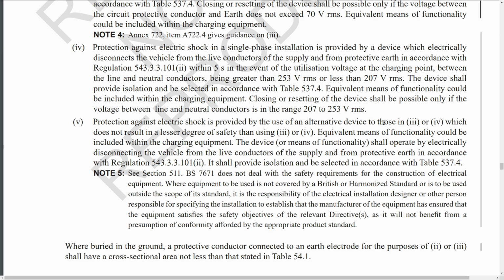Now, this can happen by having an unbalanced three-phase system, because when you have an unbalanced three-phase system, the neutral point is not actually at the neutral point anymore. It tends to move away, and the voltage on that can actually be higher. And you might think, well, a domestic property or single-phase installation doesn't have any three-phase in it. Well, of course it does, because most domestic properties, although they have single phase in the property, that supply is actually from a three-phase supply in the street, and it's quite often the case that you have a row of houses. Say the phase is connected at one house, the next house has the other phase, and then the third phase in the third house, and then it just repeats like that down the road.